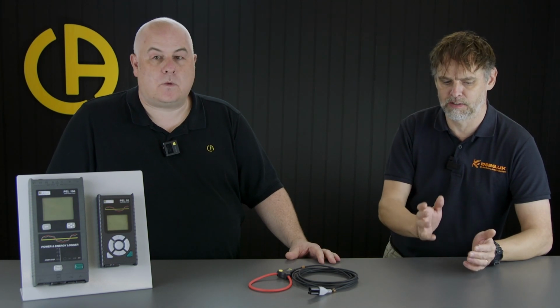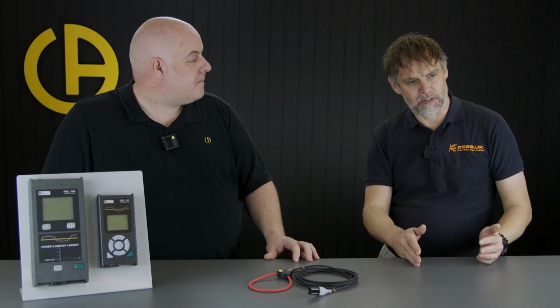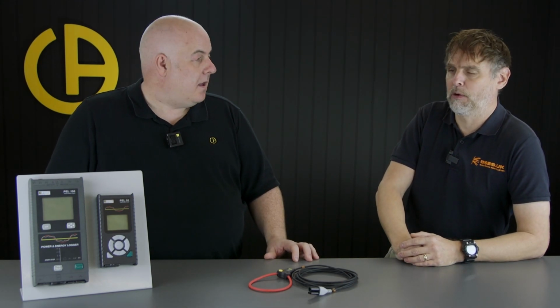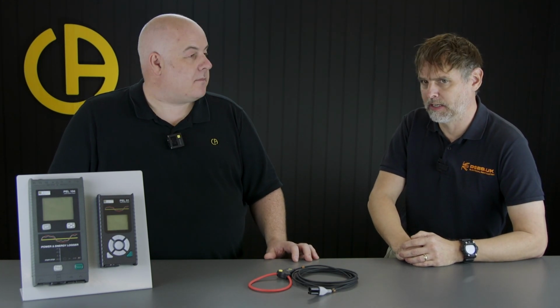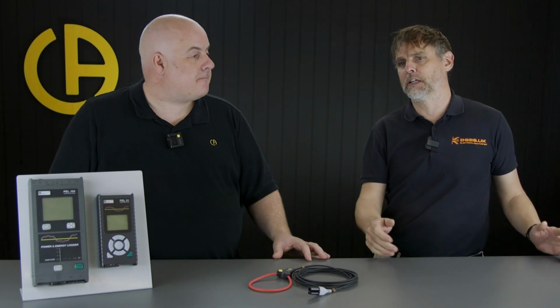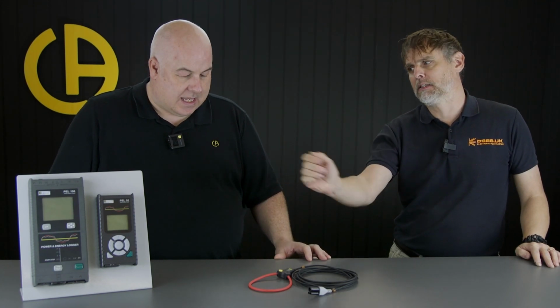There have been many a time we've been called out for trip faults that are intermittent, and obviously if the thing isn't tripping or blowing or failing while you're there with your instruments in hand, then it can be quite tricky to track down what's going on. You can do a bit of detective work, a bit of sleuthing around, you can get some baseline test numbers and some data from the site, but you kind of got to catch it in the act. And if you're not there to catch it in the act, well, you need something to do it for you.